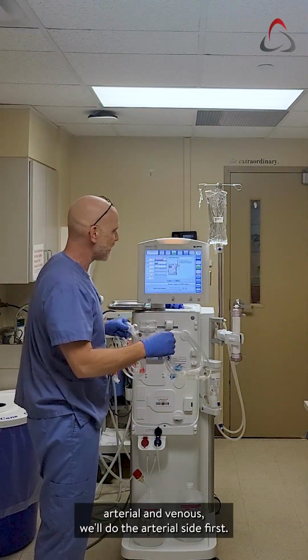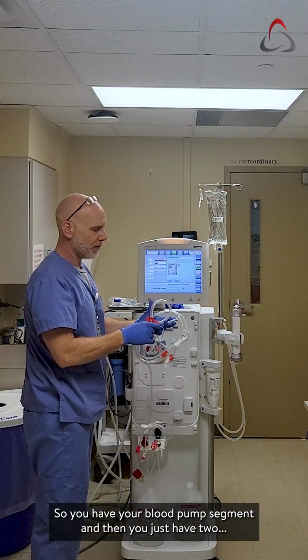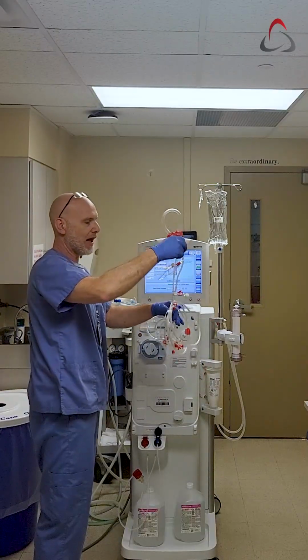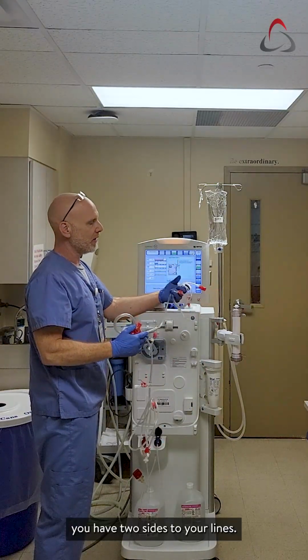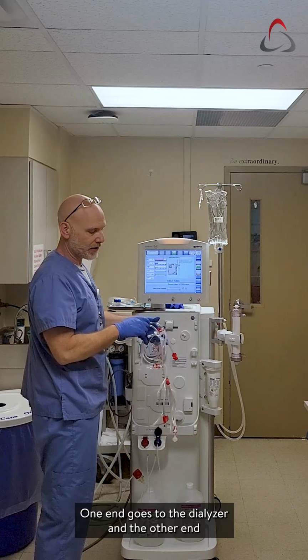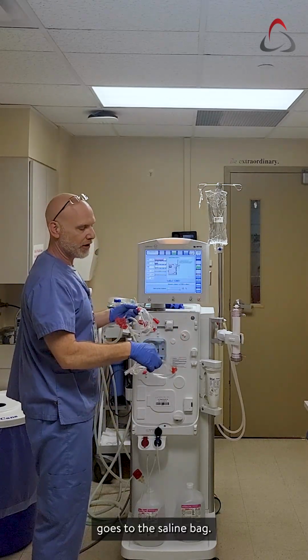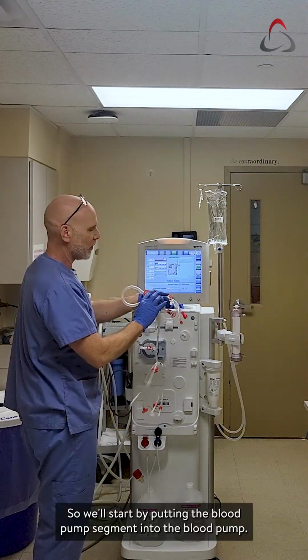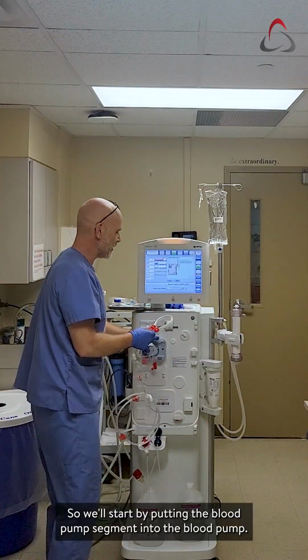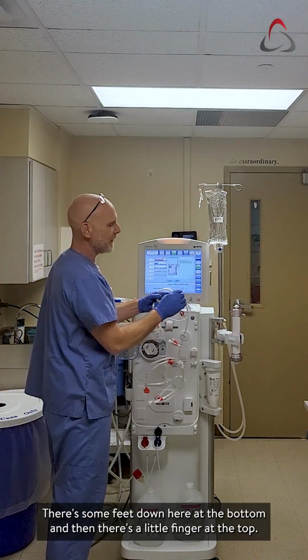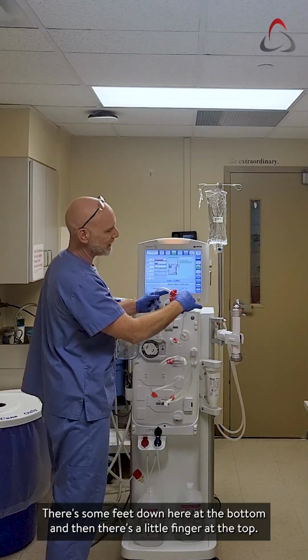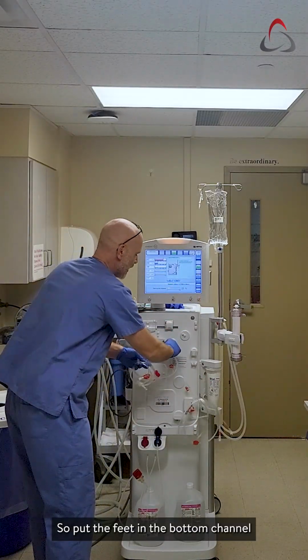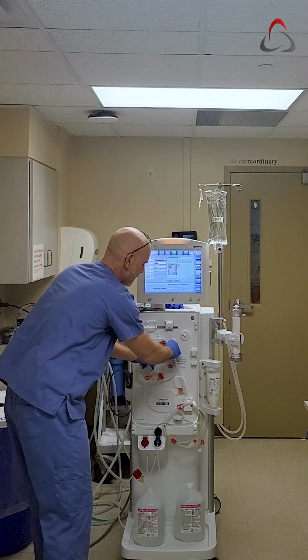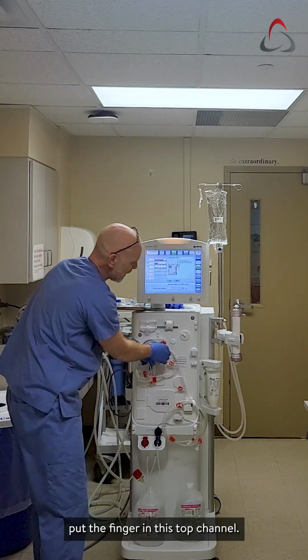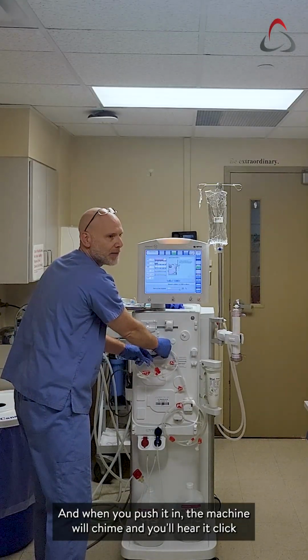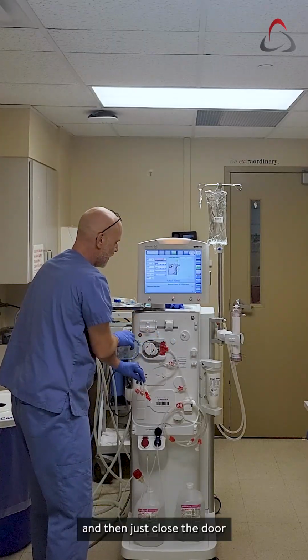So the blood lines come arterial and venous. We'll do the arterial side first. So you have your blood pump segment, and then you have two sides to your lines. One end goes to the dialyzer, and the other end goes to the saline bag. So we'll start by putting the blood pump segment into the blood pump. There's some feet down here at the bottom, and then there's a little finger at the top. So put the feet in the bottom channel and put the finger in this top channel, and when you push it in, the machine will chime and you'll hear it click. And then just close the door.